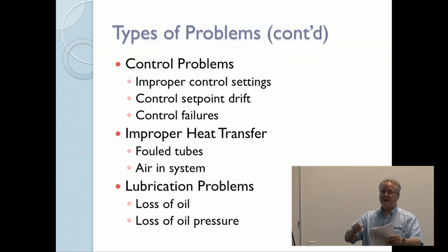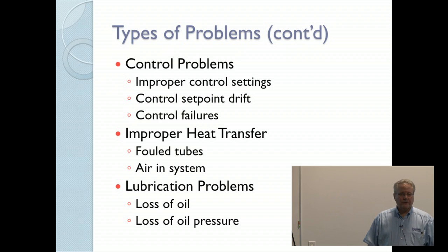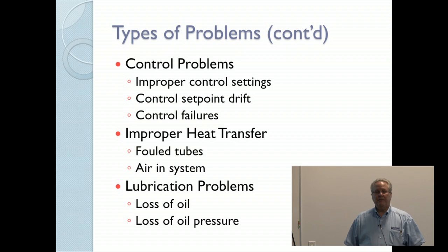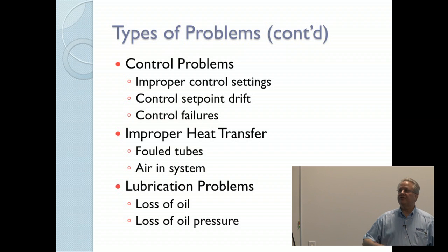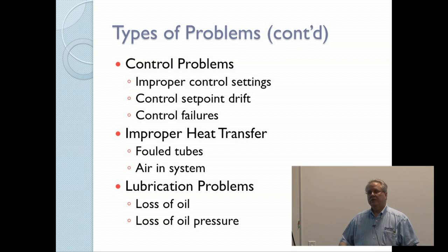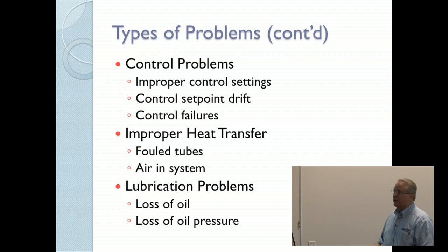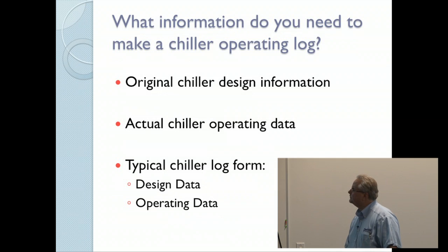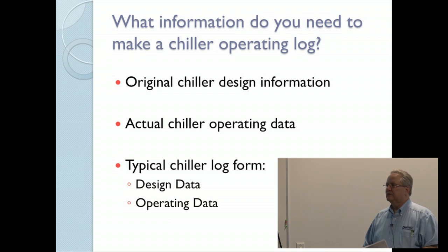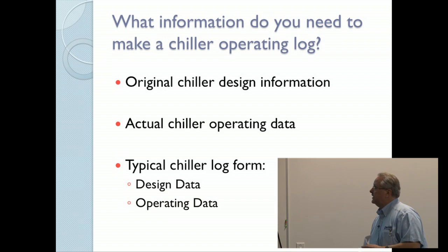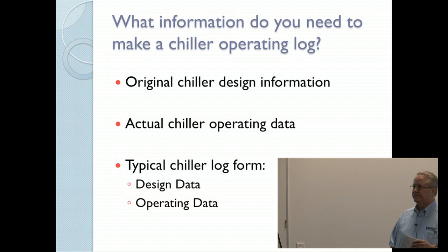Maybe there's a sensor that's kind of separated itself from the pipe a little bit and not getting a good reading anymore. Improper heat transfer. You might be able to identify fouled tubes, or if there's air in the system. Lubrication problems, loss of oil or loss of oil pressure. So those are all the kinds of things that you can find potentially with analyzing a good, at least daily operating log. What information do you need to make a chiller operating log?